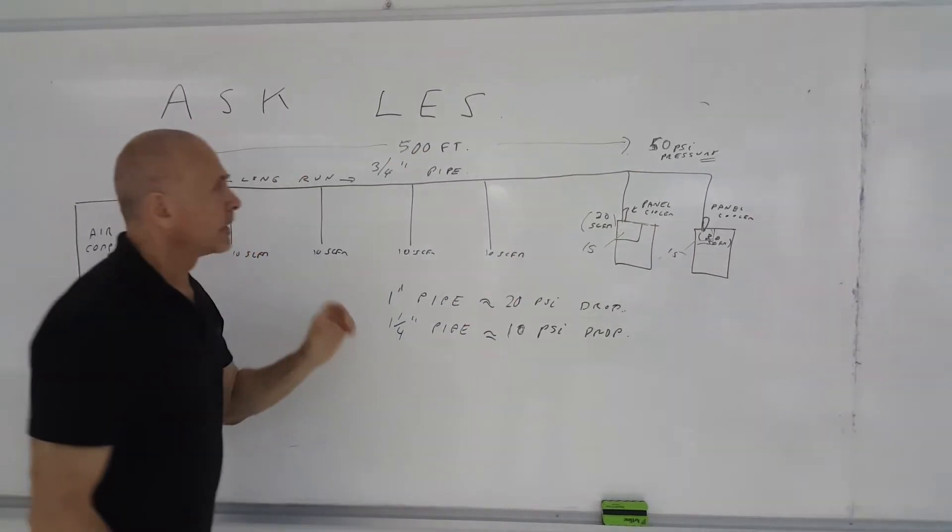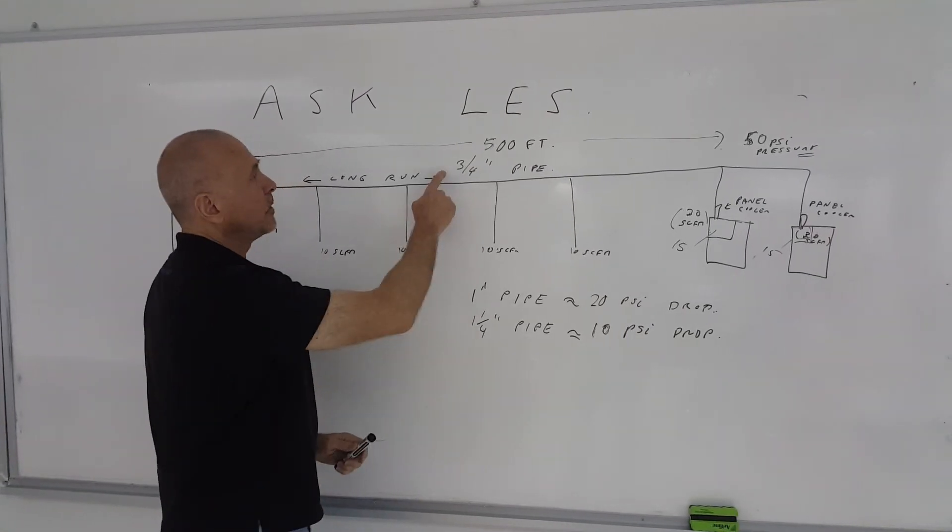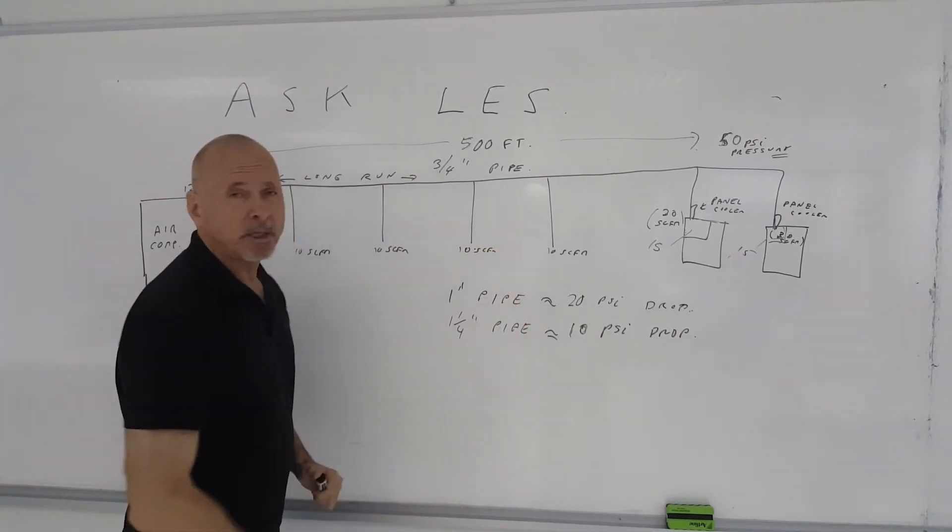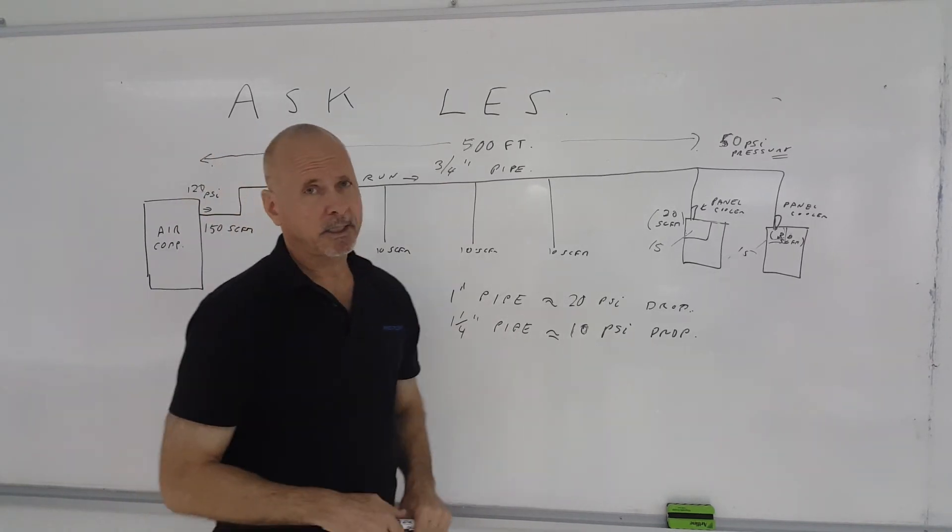So, you have to look at the system. Now, imagine if they had a one-inch pipe instead of three-quarter inch, that 50 PSI pressure drop would only be about 20 PSI. If it was one and a quarter inch pipe, it would only be a 10 PSI drop.